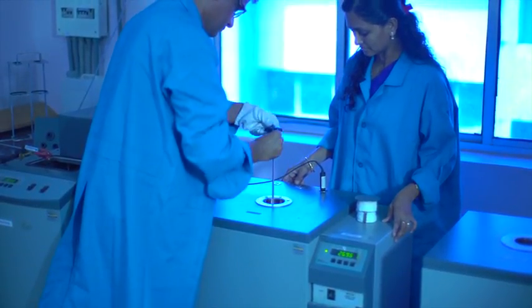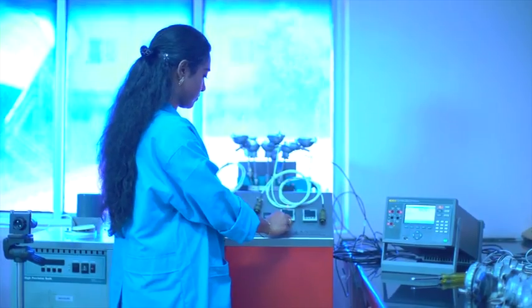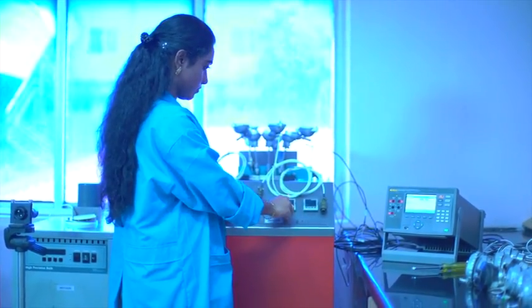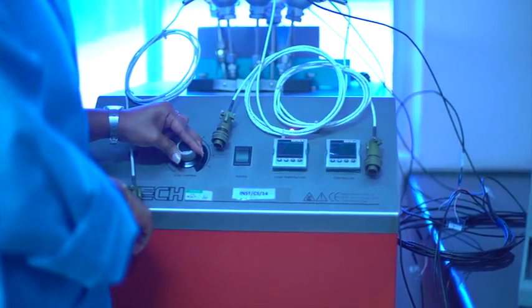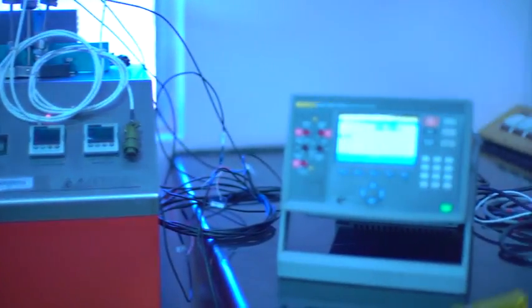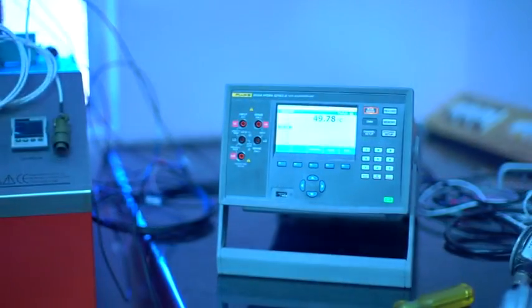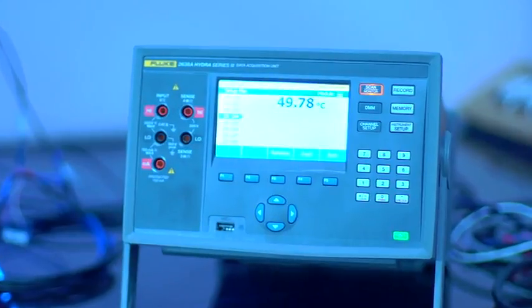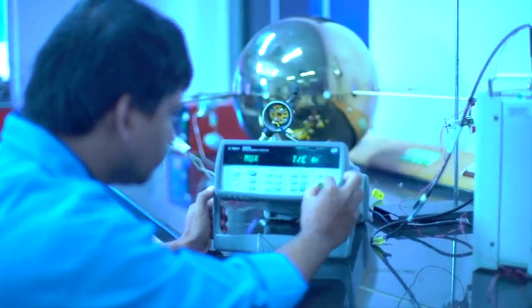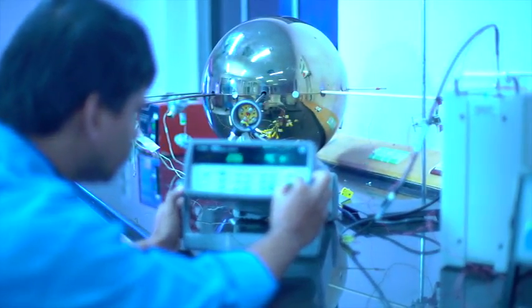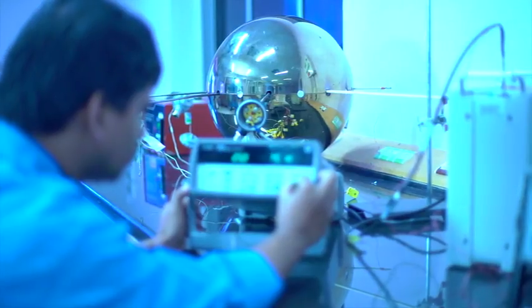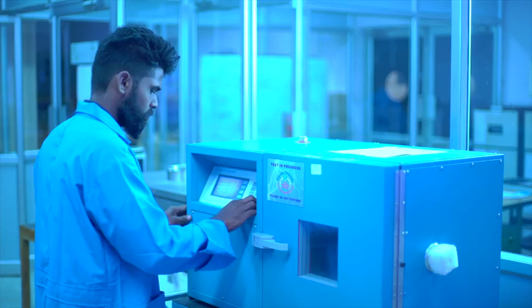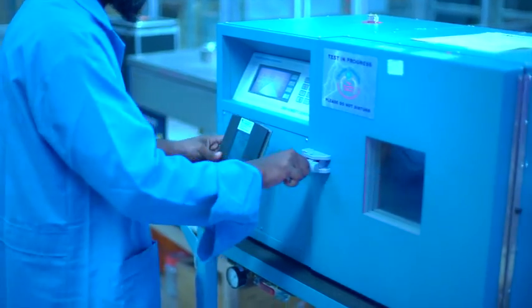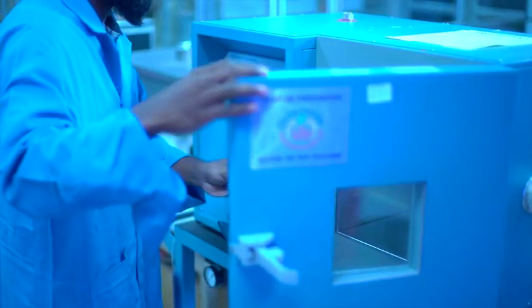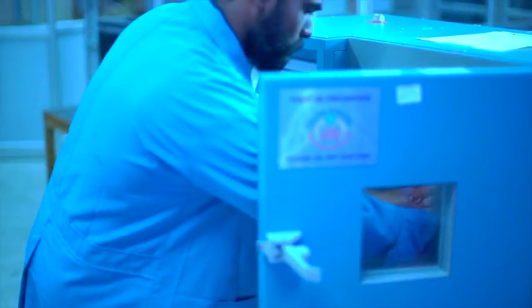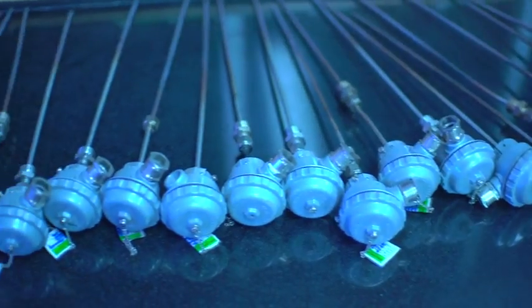The ITS fixed point calibration is done in the range of -38 to 960 degrees centigrade, while comparison calibration is done at -70 to 1200 degrees centigrade and at boiling point of liquid nitrogen. Humidity calibration facility provides very accurate calibration of humidity meters. The lab also undertakes on-site calibration.